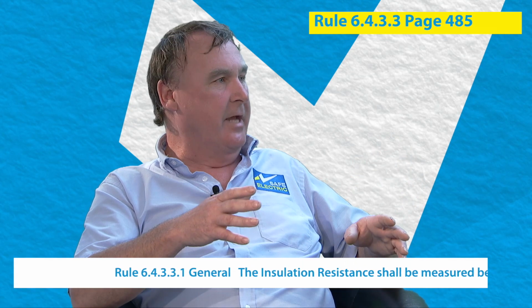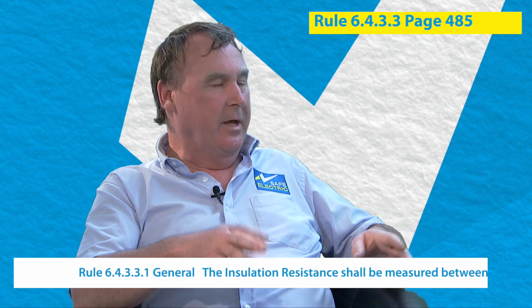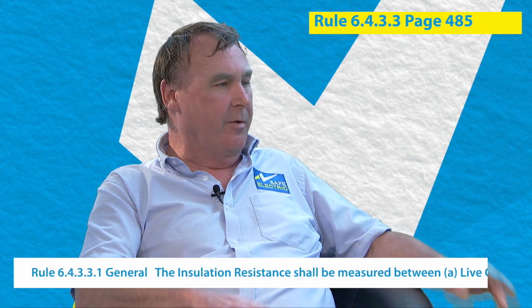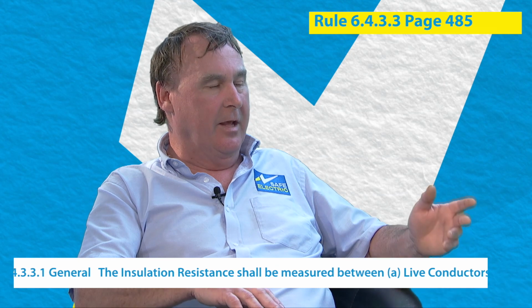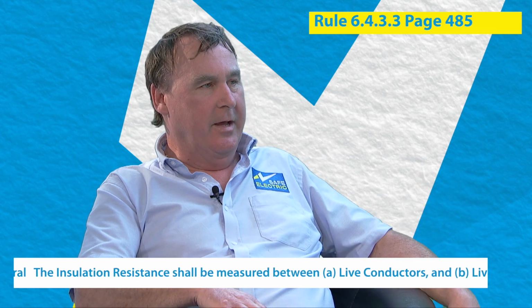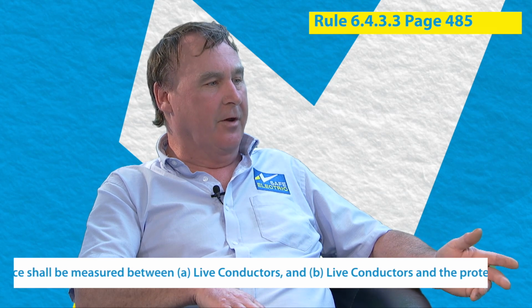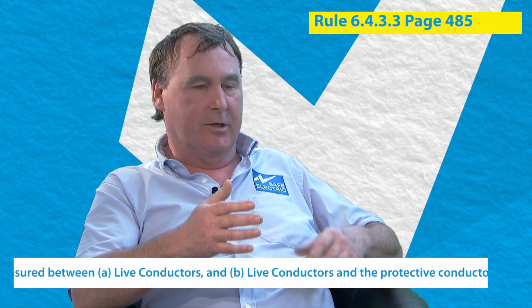The new rules also require that we carry out an insulation resistance test. The minimum value of 1 mega ohm, which we must achieve, remains the same. Yep, that hasn't changed. The terminology used in describing the rule is slightly different. In the previous ET 101, they spoke about checking each live conductor to the protective conductor and making sure that you had electrical separation there of 1 mega ohm.